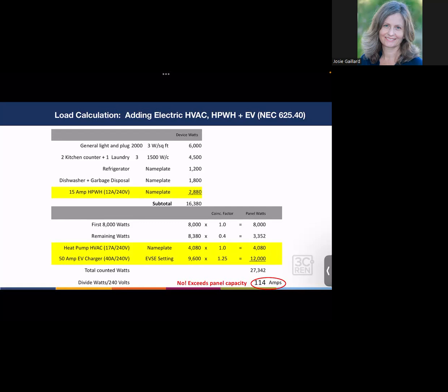These 2 devices coming up next, the heat pump HVAC and the 50 amp car charger, have these special coincidence factors, and the code describes them carefully. So the first applies to HVAC. The larger of the heating or the cooling load gets a coincidence factor of 1.0. So, unfortunately for us, we're trying to fit as much as we can onto a panel. The code says all those 4,080 device watts become panel watts. So you can see on the far right there, we add 4,080 watts.